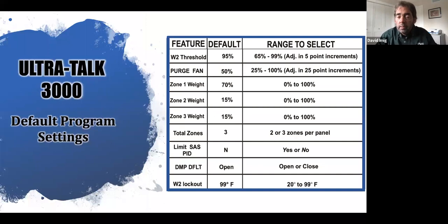Purge fan means once the call has ended in that particular area, my fan operation is at what speed. When I'm purging, I bring the fan down to 50% operation during that purge time, which is 180 seconds. So at the end of a call, for 180 seconds, I will bring that fan down to a 50% level.